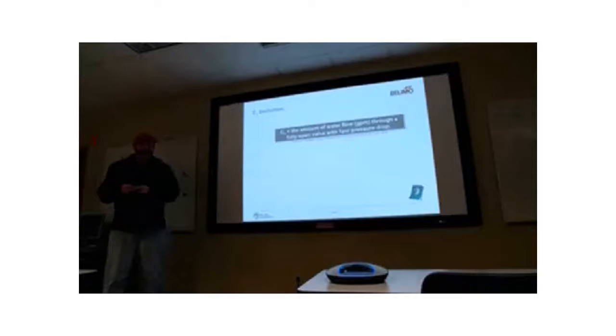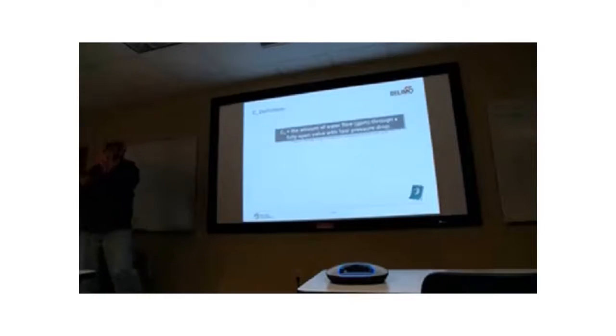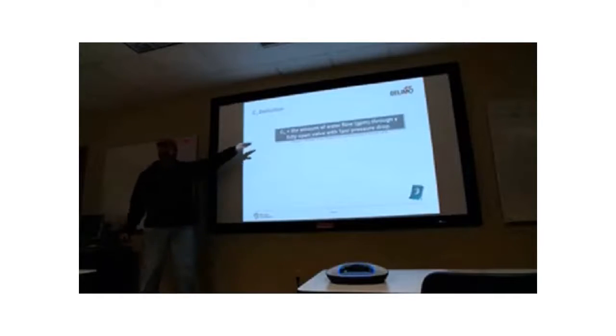So the design data. Here's where we get into what I call the egghead stuff, the engineering stuff. When you select a pressure-dependent valve, you have to deal with this thing called a CV. Anybody heard that term before? Nobody? Okay, think of the CV like this. The CV is the amount of water that goes through that valve when it's fully open for a given pressure drop. You have to drop pressure across that valve in order to control the flow. This CV gives you an indication of how much water you're going to get through that valve at a certain pressure drop. The definition is the amount of water through a fully open valve at a 1 psi drop.